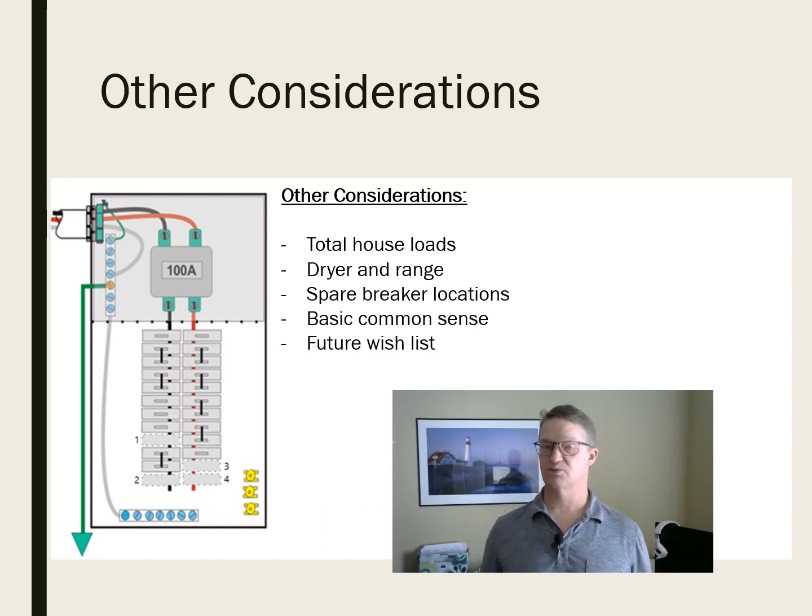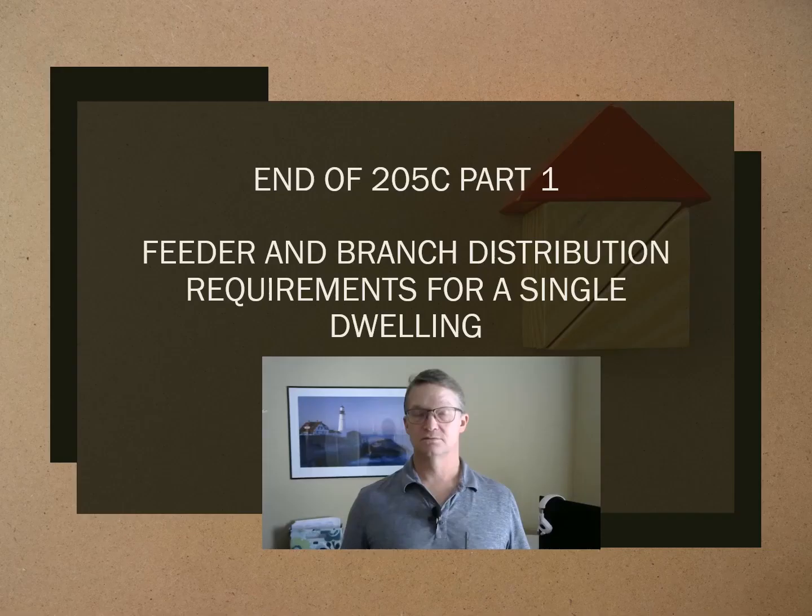Even though code says that we have to have a minimum of 4 breaker spaces left open, the customer may want more breaker spaces depending on what their future plans are going to be for their house. For example, if they do not have a developed basement right away, we're going to leave more than 4 just to accommodate any other loads they want to put in there.